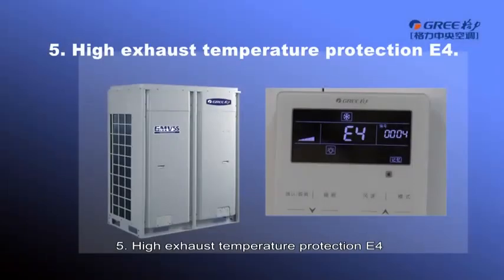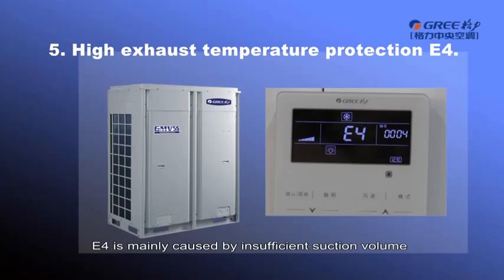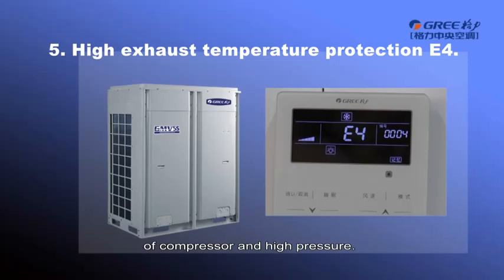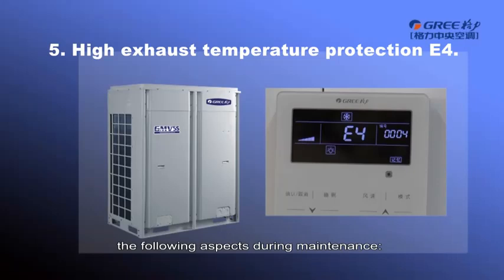High Exhaust Temperature Protection E4 is mainly caused by insufficient suction volume of the compressor and high pressure. Therefore, please check and solve the problem from the following aspects during maintenance.